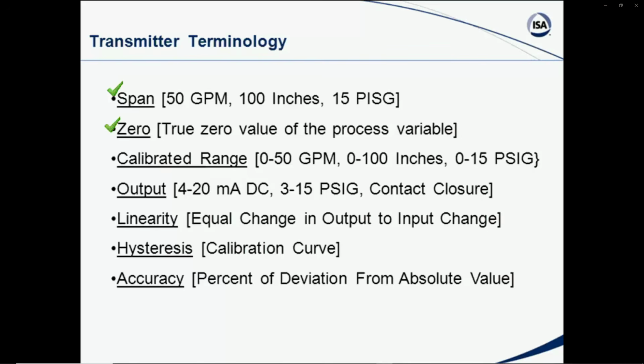The calibrated range, again, 0 to 50, 0 to 100. It's a from and to. The output, then, that we would get analogous or proportional to that particular calibrated range would be 4 to 20 milliamps, 3 to 15 psi. Could be contact closures, digital outputs. It could come in a lot of different range circumstances there.